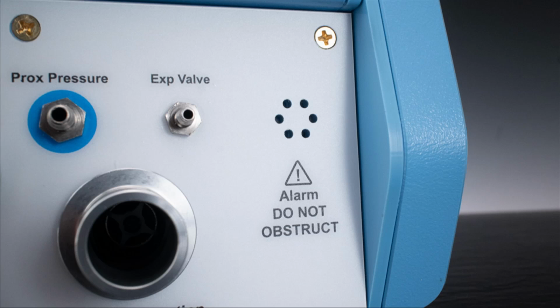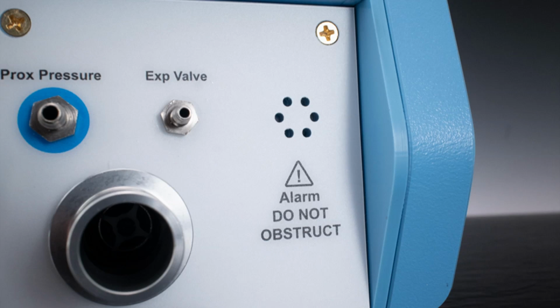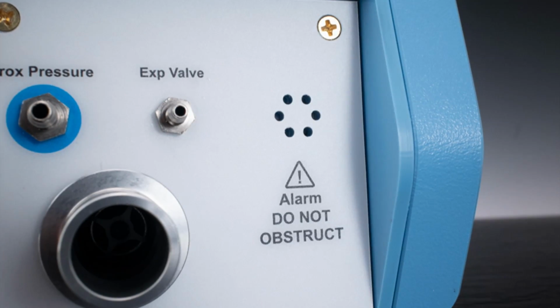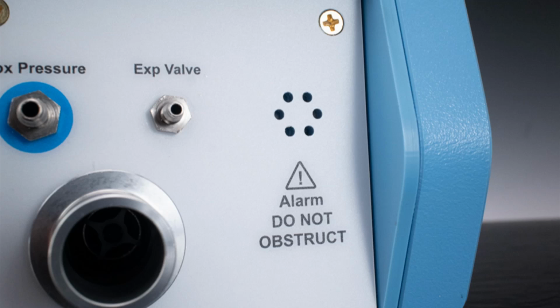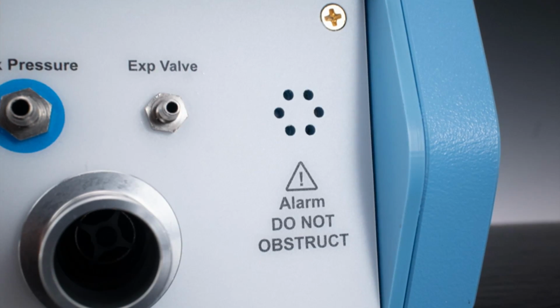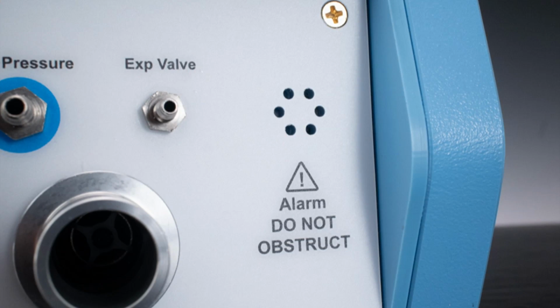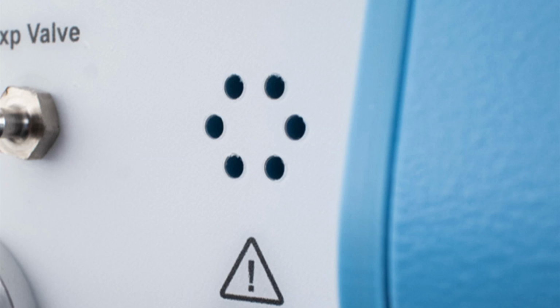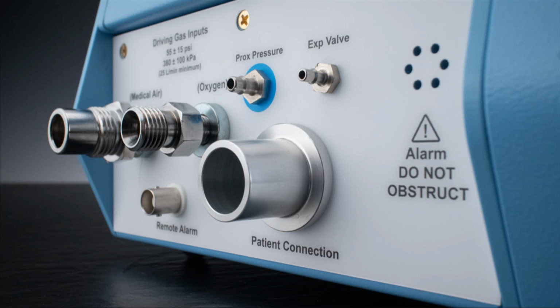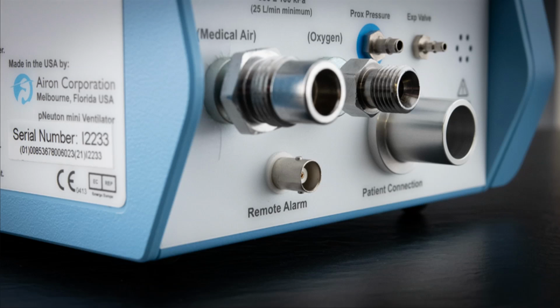Audible alarm. The audible alarm for the pNeuton Mini can be identified by 6 small holes where the alert sound is emitted. Please be sure to never put anything in these holes or cover them up, otherwise the alarm will not be audible. This is what the alarm sounds like. The alarm will sound when there is a patient disconnect, high pressure alarm, or the source gas, oxygen, or air pressure drops below 40 psi.